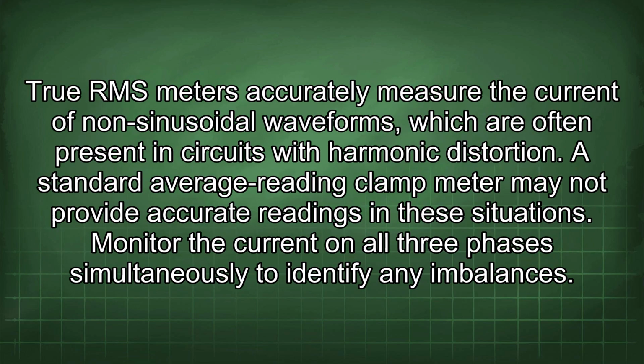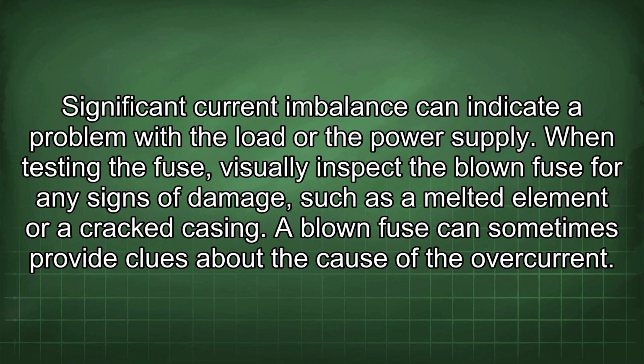True RMS meters accurately measure the current of non-sinusoidal waveforms, which are often present in circuits with harmonic distortion. A standard average reading clamp meter may not provide accurate readings in these situations. Monitor the current on all three phases simultaneously to identify any imbalances. Significant current imbalance can indicate a problem with the load or the power supply.